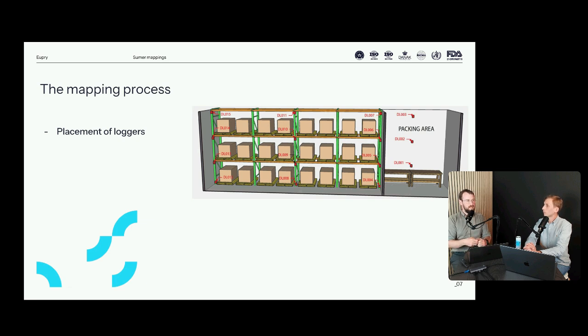So in my view, a much more risk-based approach should be used for placing data loggers. It should be grid-like because we want to ensure the temperature is homogeneous and within acceptable ranges for all placements within the facility. It's not to fulfill guideline specifications of where to place sensors, it's to mitigate risk. That's really important to keep in mind.